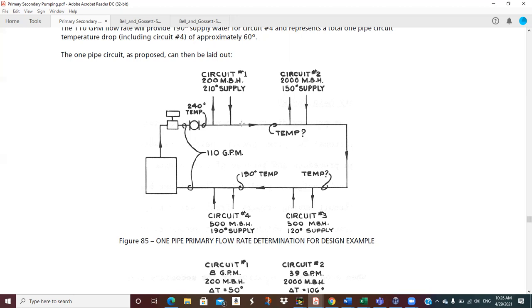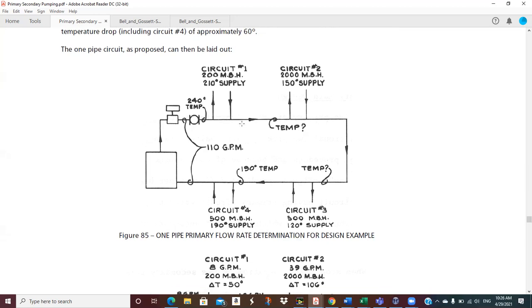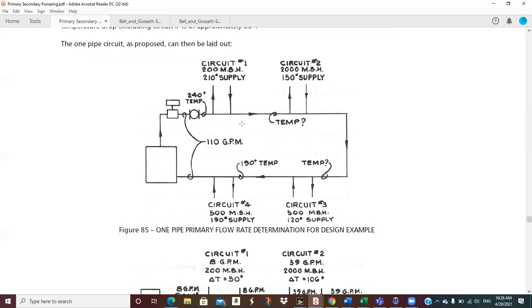It's a one-pipe primary, and every time you go across a secondary, you lower your water temperature. Well, those poor guys out there on the end of the system, it's cold in here, give me some water. I started out at 240, but that's on the other side of the building. All of that has to be taken into consideration, and he does that very carefully as he goes through it. But I'm just not sure this is very practical.